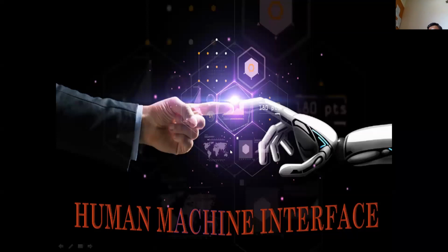Okay, coming to the HMI. There is no greater difference between the SCADA and the HMI. Mostly the SCADA uses software on a PC, whereas the HMI is a small screen. You might have seen the HMI. It's a touchpad screen, so you can touch and control the things.